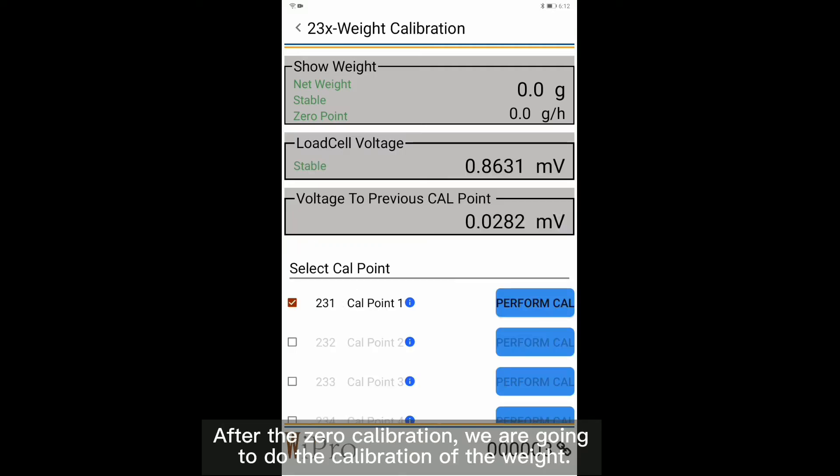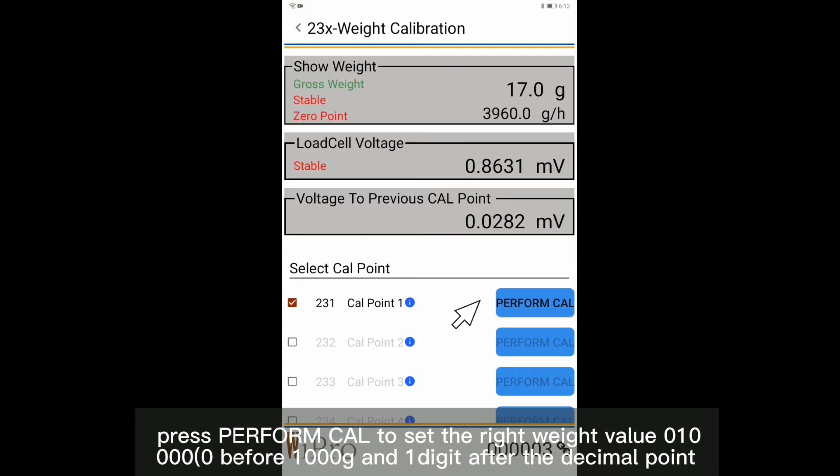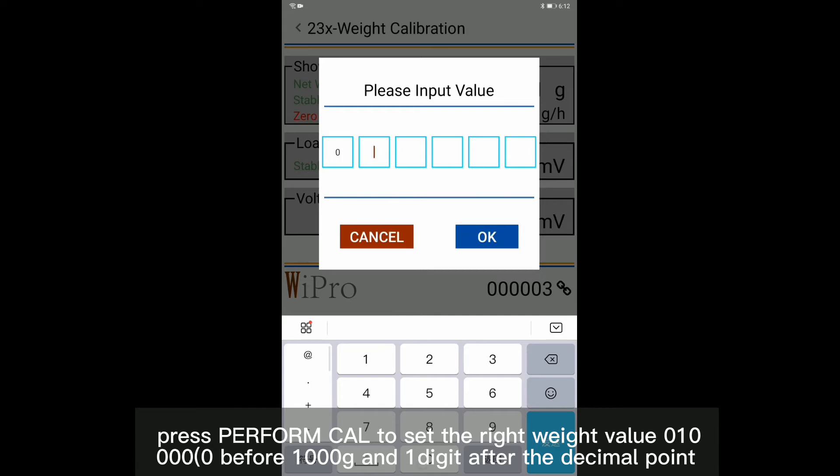After the zero calibration, we are going to do the calibration of the weight. Put a one-kilogram weight on the weighing platform. Press Perform Cal and set the right weight value to 010000.